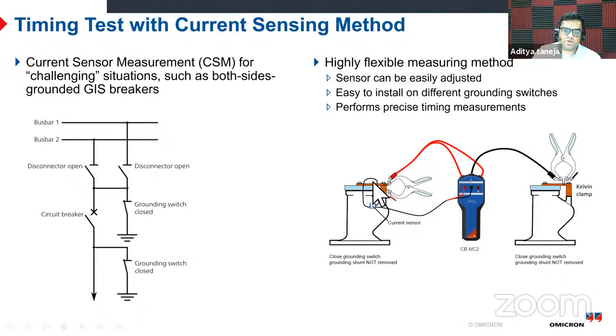So if we can avoid that in inspections, that's good, because then if this indicates that there is a problem, then we have the justification to make that extra effort to take a shutdown and do a proper analysis of the contact health and the condition of the breaker. Also, when you are doing inspection, you have to test all the bays. So let's say there are 50 bays and only 1 or 2 of them show some deviations in timing, then you just have to take a shutdown, or a longer shutdown, for those two, remove that ground link and do that extra effort for testing.